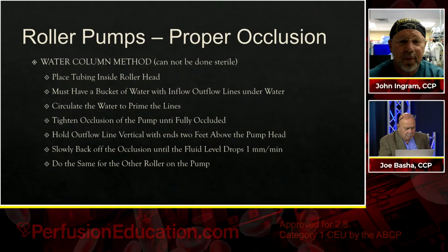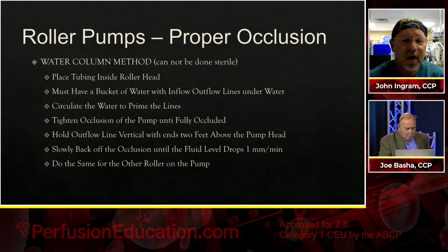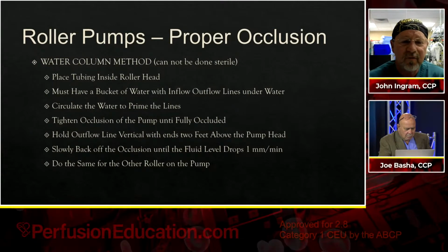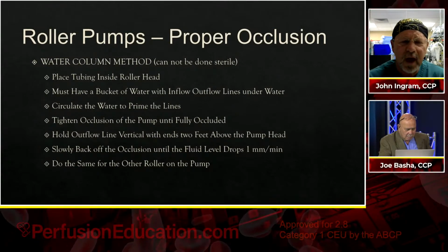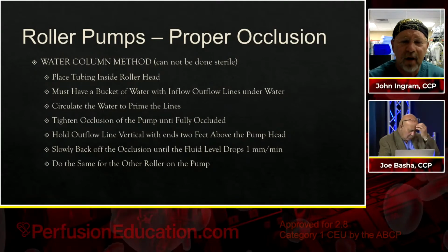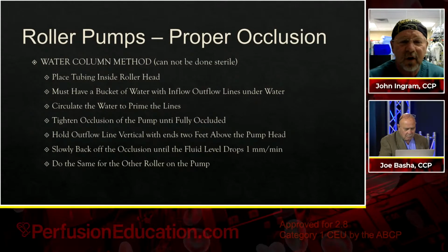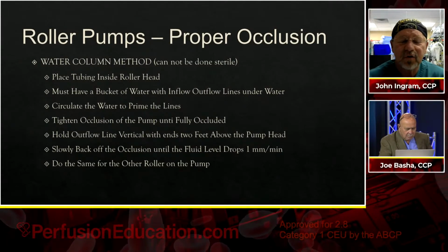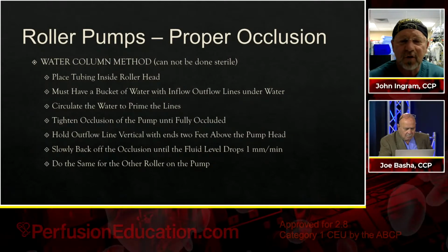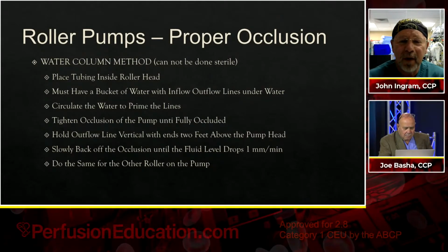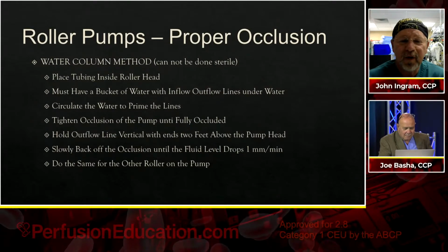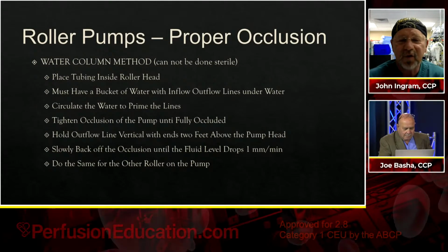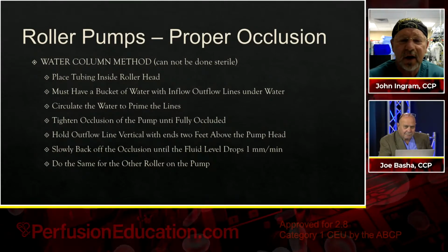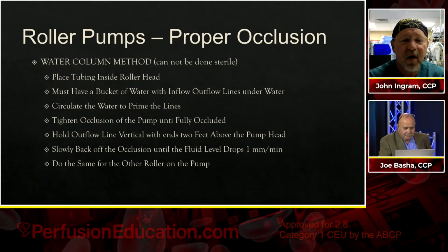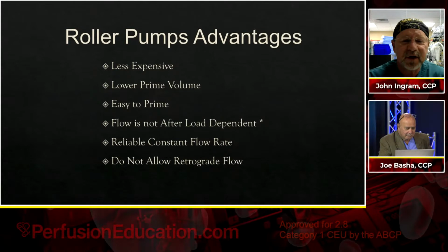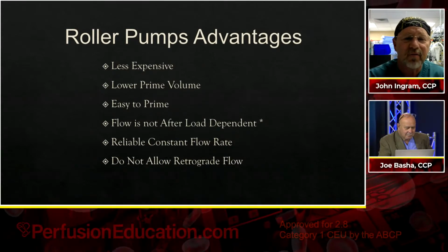You then tighten the occlusion of the pump until it's fully occluded again. Then you take your outflow line and you hold it in your hand, hold it vertical with the ends of that tubing about 2 feet above the level of the pump head. Then you slowly back off your occlusion until the fluid level drops ever so slightly. Textbooks and articles will tell you something like 1 millimeter a minute, which is just barely moving. I don't think anybody could actually time that, but it gives you the idea that you want it to be ever so slightly dropping. And then, of course, try to do the same thing for the other roller on the same pump. This is basically the two styles that people out there use, or versions of them.